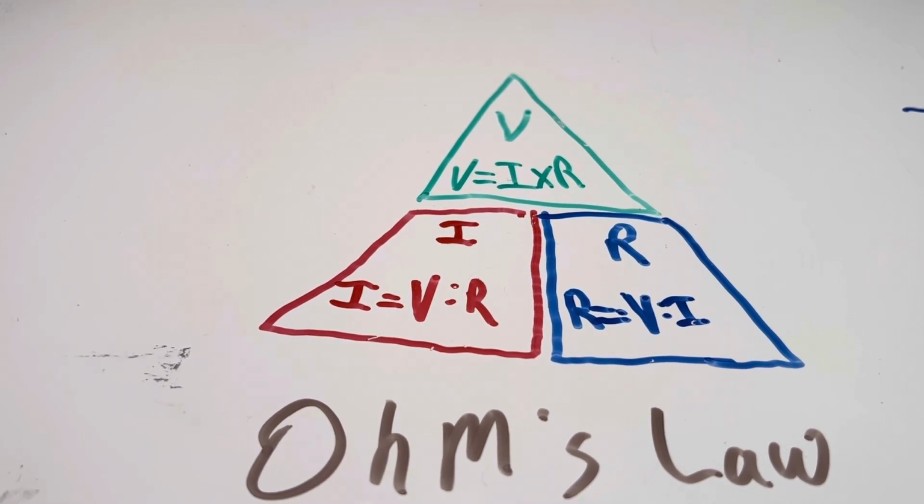So let's say you have a 120 volt heating coil that you go to and you measure, let's say it's a 20 amp coil. You measure that it is at 19.5 amps, so almost its full load. Voltage is actually measuring in at 82 volts. So that tells you that there's got to be a problem with the coil.